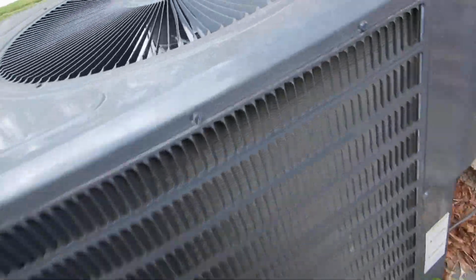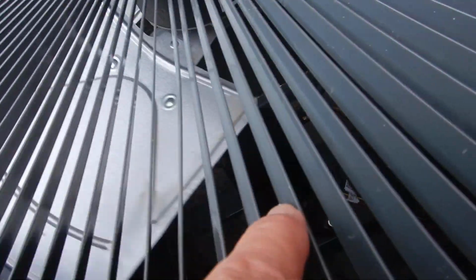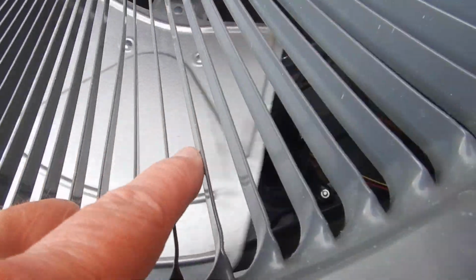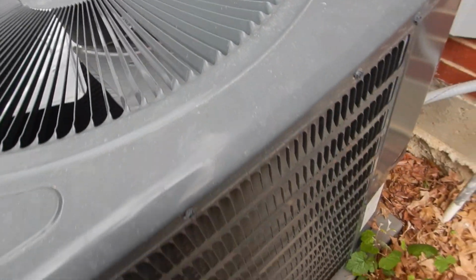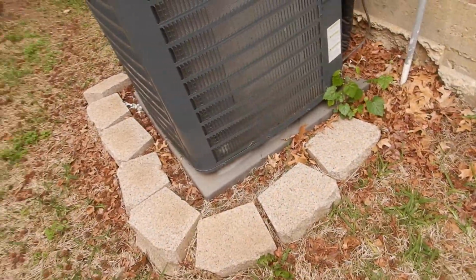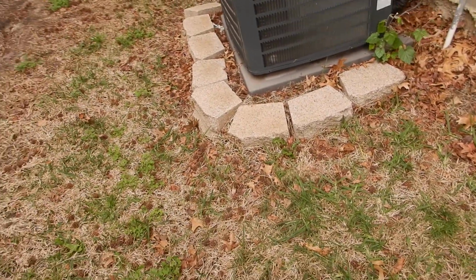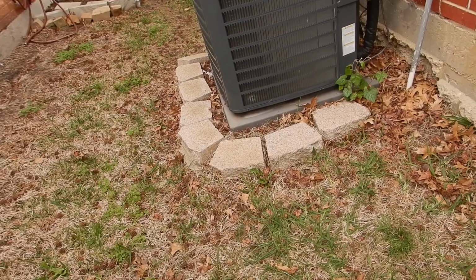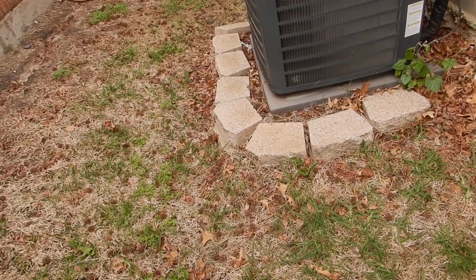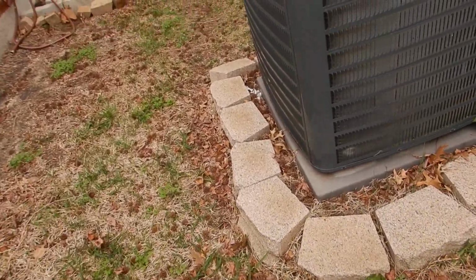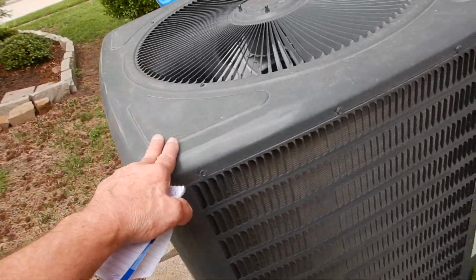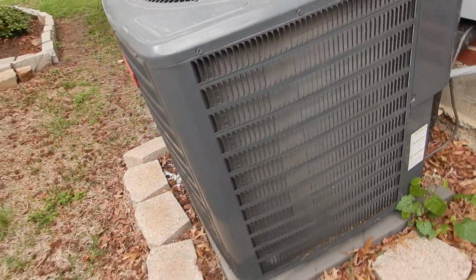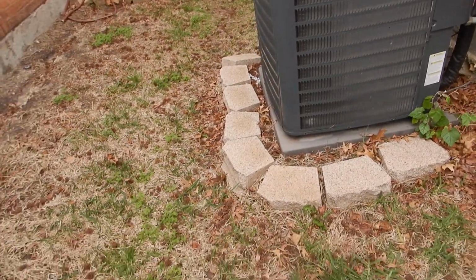The manufacturer does not make compressors for this anymore. So if the compressor goes, the whole condensing unit needs to be changed. And the same thing might be true with some of the metering devices at the indoor air handler and some of the refrigerant piping, depending on which refrigerant you're replacing it with. So it's imperative this be maintained and continue for as long as it can.